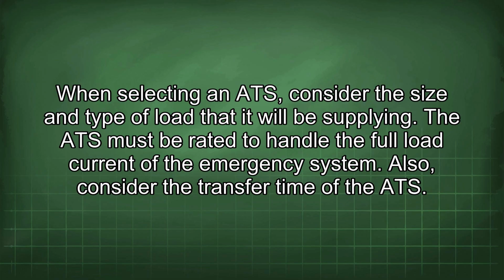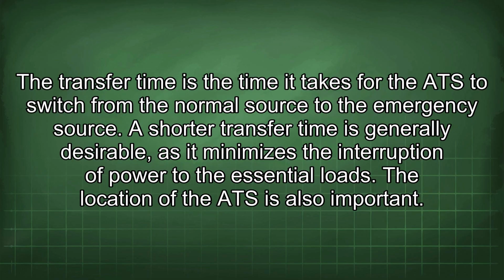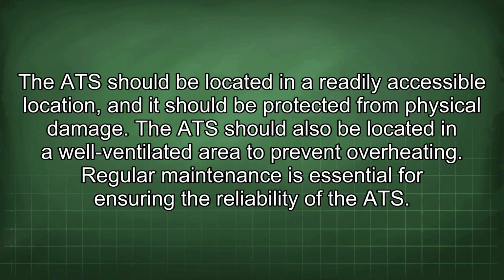The ATS must be rated to handle the full load current of the emergency system. Also, consider the transfer time of the ATS. The transfer time is the time it takes for the ATS to switch from the normal source to the emergency source. A shorter transfer time is generally desirable, as it minimizes the interruption of power to the essential loads. The location of the ATS is also important. The ATS should be located in a readily accessible location, and it should be protected from physical damage. The ATS should also be located in a well-ventilated area to prevent overheating.